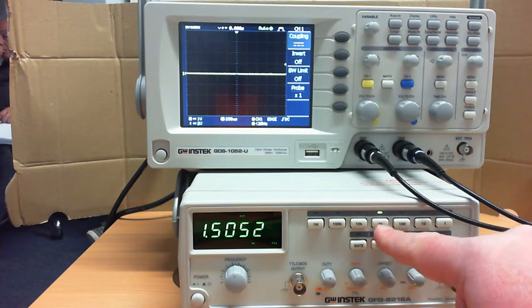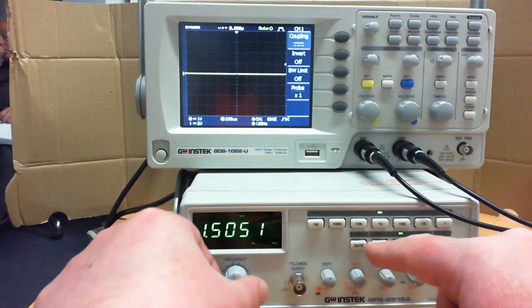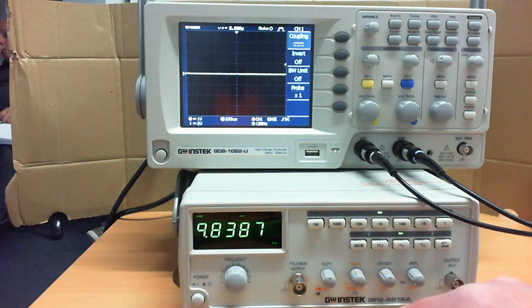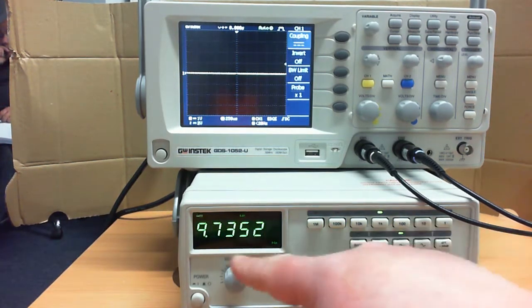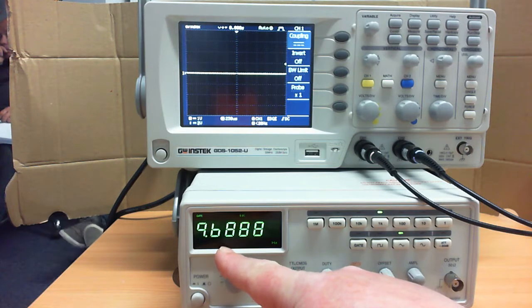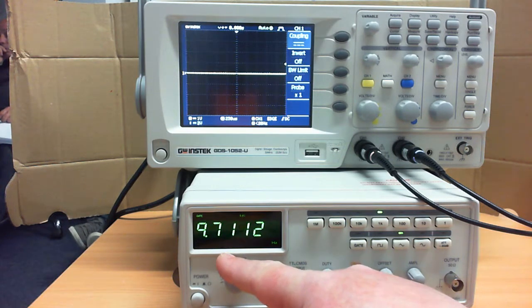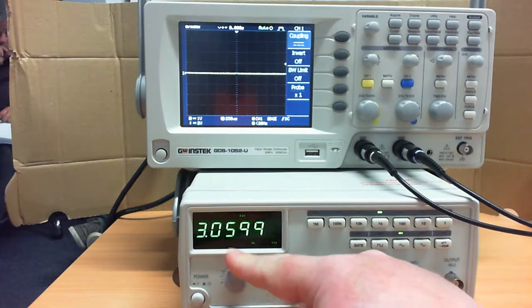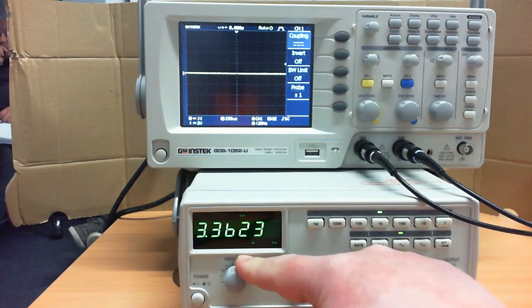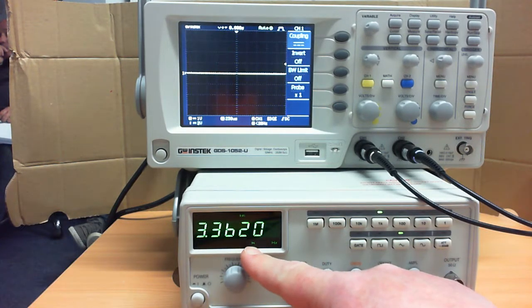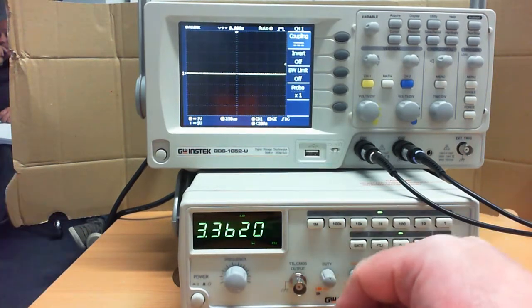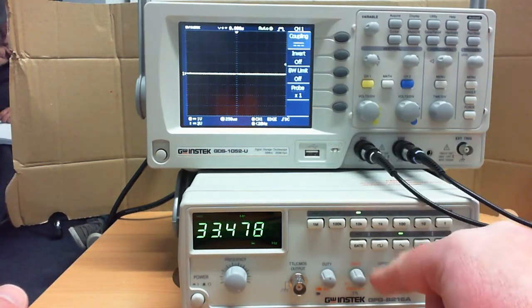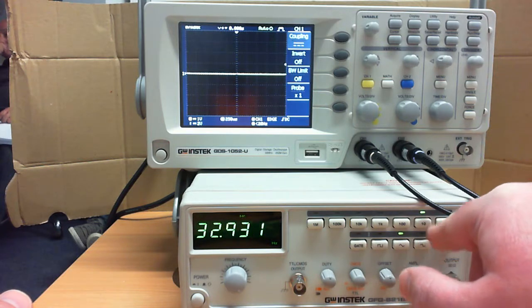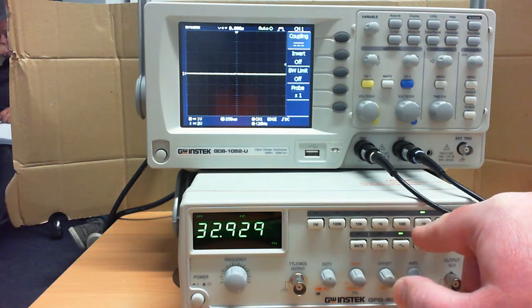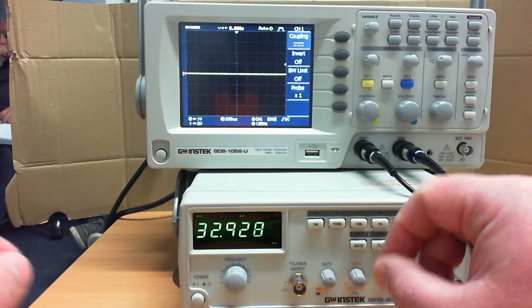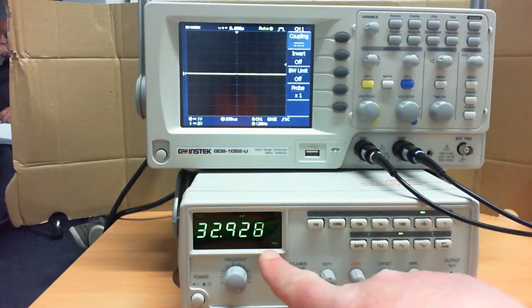All right. So if I go to the 1 kilohertz, which I have here, if I bring my frequency knob all the way down anti-clockwise, I can start at 10 hertz or 9.6 hertz. Okay, and the max I can go to is 3.3 kilohertz. Okay, and that range from 1 to 3.3 essentially runs through all the ranges. So it doesn't matter which range I select. The max min nominal numbers don't change, but the amplitude changes.